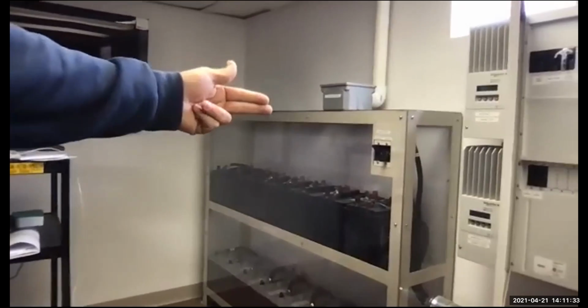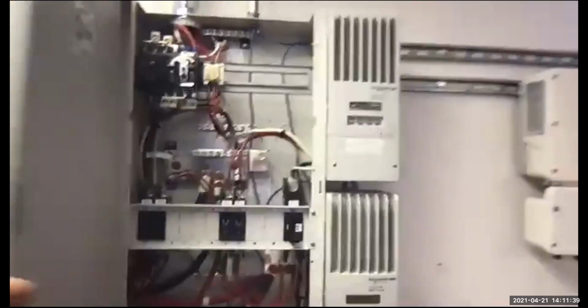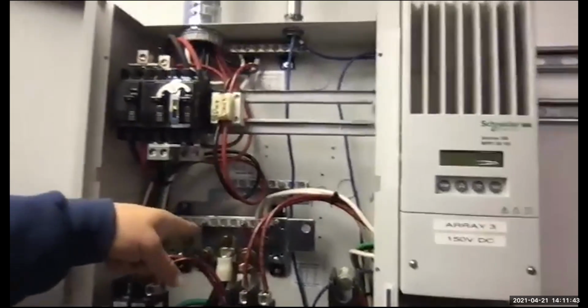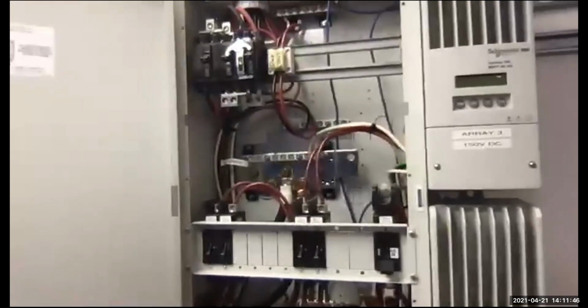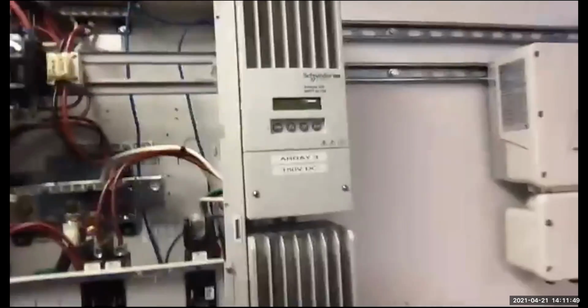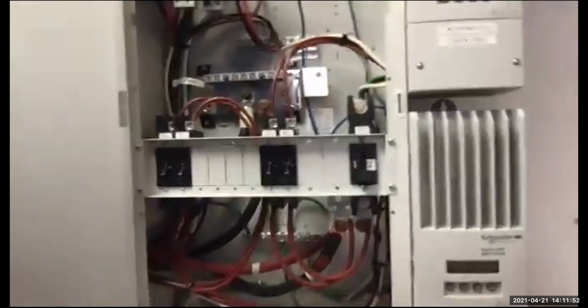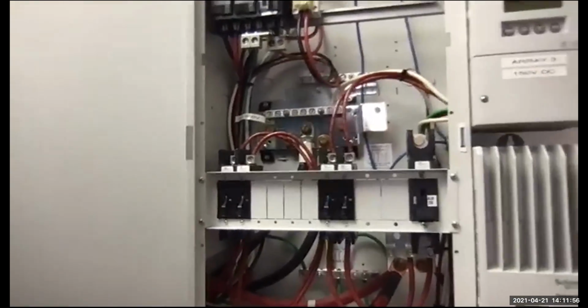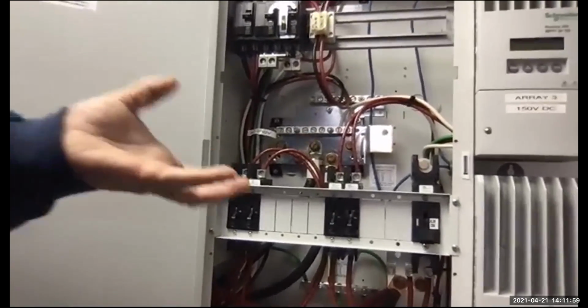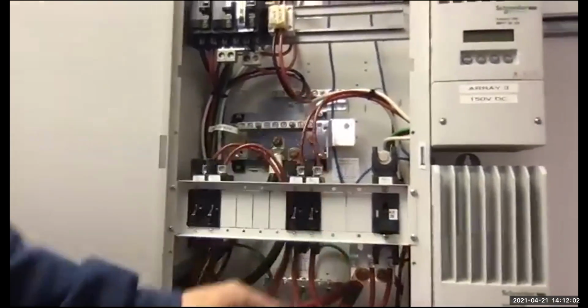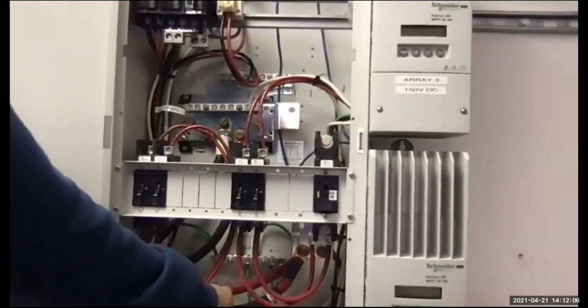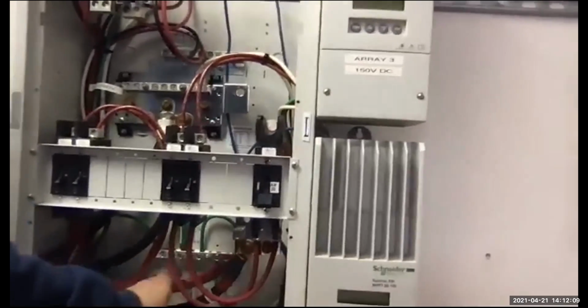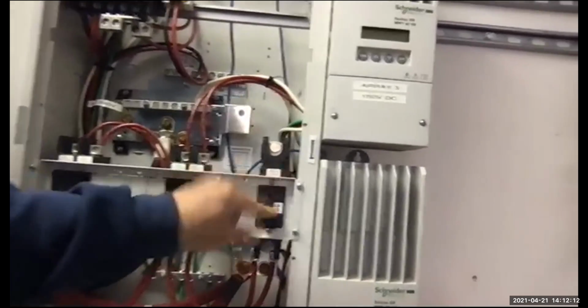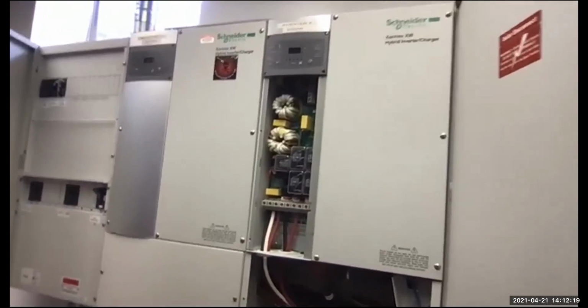We know we've got a negative and a positive cable coming this way from the batteries. It runs through our trough, and then the negative cable goes to the negative DC bus right here. Then our positive cable goes from this to our positive DC bus right here. So what matters is when we shut this off, we're disconnecting our battery from this cable, which connects to our inverter. So these two cables are disconnected by this breaker. That's what those guys are putting in first. Okay, even though we don't have any batteries, they still need that bar up there.